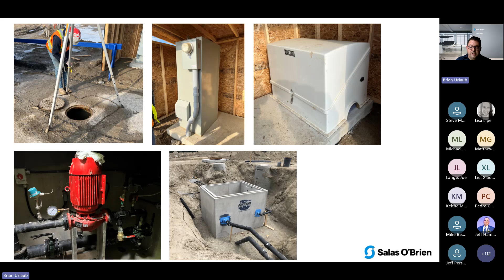Again, a few lessons learned here. Number one, below grade vaults with pumps and so forth down in a high humid salt environment. You definitely have to treat or coat or insulate, make sure everything is completely sealed to prevent corrosion, because you will have corrosion. So that's definitely a key thing if you're going to do below grade vaults with more than just pipes in those vaults, like not a typical vault from a ground loop heat exchanger, but actual pumps and other components.